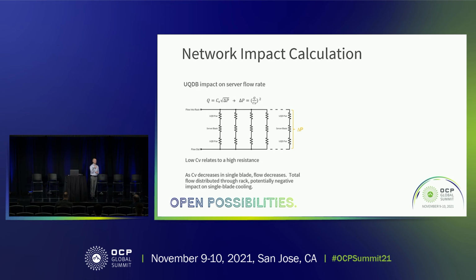So that means that for a given flow, your 8th server would have a higher pressure drop. But if we look at this system, you can assume the pressure for the flow into the rack is one pressure, and the pressure at the outlet from the rack is another pressure, right? So the pressure drop has to be equal across every blade. The only way that can be true is if the flow actually decreases through that 8th server. So that's the worst case scenario. Let's say you have 7 really great universal quick disconnects that far exceed the specification, and an 8th that just meets the minimum requirement. Are you going to have problems cooling that 8th blade?